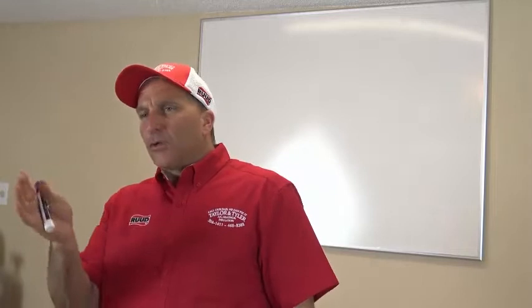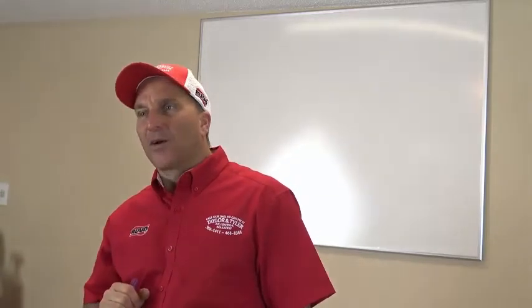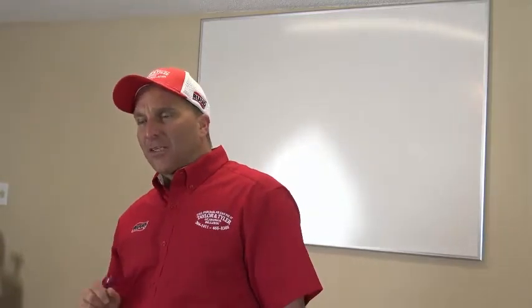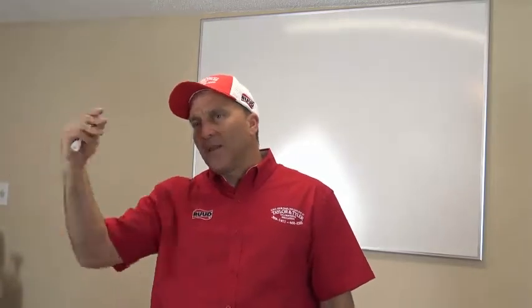Now, let's loosen up some of the connections on it. Now it's going to start getting hotter and hotter and hotter and hotter. And finally, you start burning the fuse. But now, let's go loosen everything up. And now let's start and put a load on that system. And if you don't get a good draw on that system, your amperage goes up. And now you blow the fuse. So there is a difference between a blown fuse and a burnt fuse.